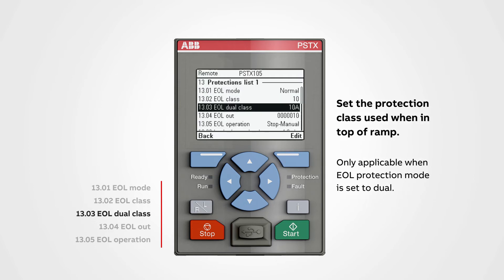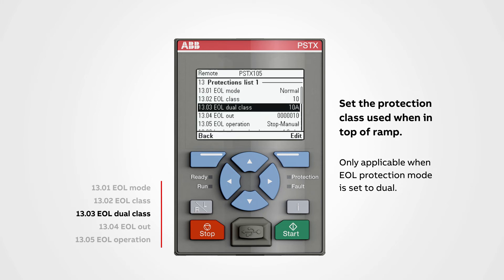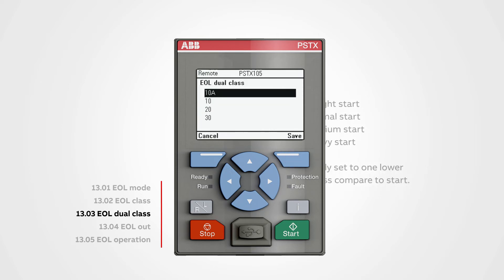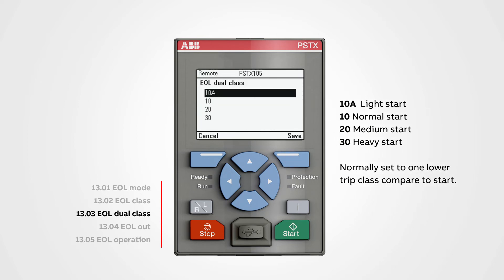EOL dual trip class: set the protection trip class when the soft starter reaches the top of ramp. This is only applicable when EOL protection mode is set to dual, and is normally set to one lower trip class compared to start.